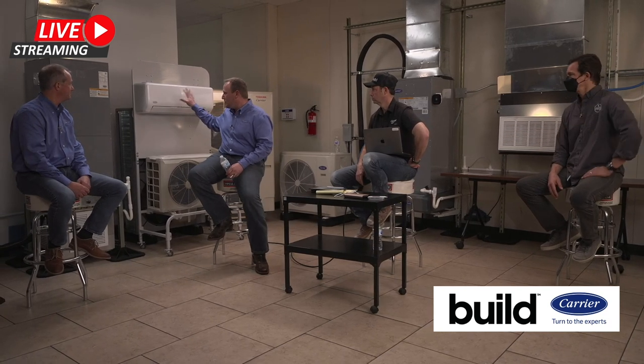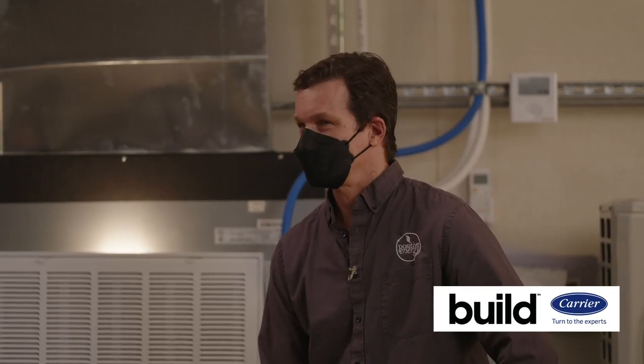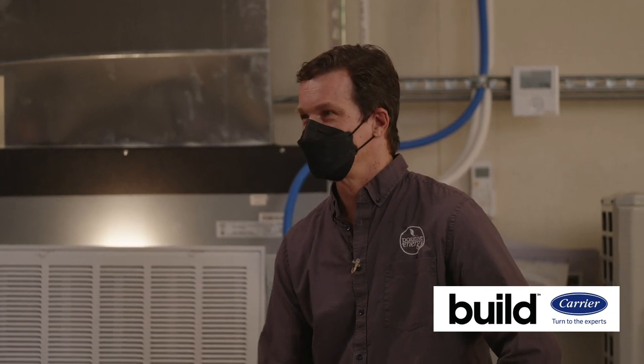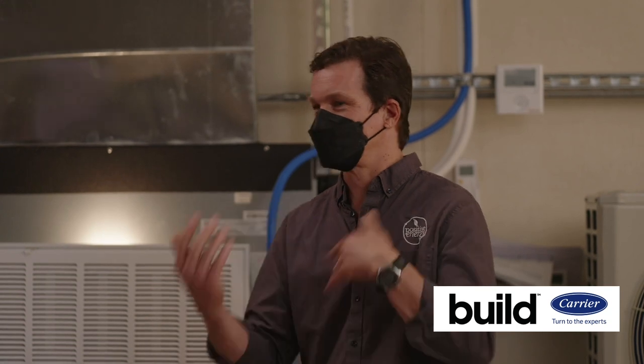But from a maintenance perspective, of course you want to clean your filter. The other thing that happens with these units, and those of you with experience with them, especially contractors and homeowners that have had them for years, eventually you're going to end up with a dirty blower wheel in here. Let me pause you for a second - in the past we've put a lot of mini splits in our houses. When you have a dirty blower wheel or a dirty unit with a coil, what's it like to get that thing clean? Oh, it's brain damage. Condensate management on these wall heads and blower wheels get caked up with dust and are just slapping the air and therefore not moving it through the space. Big problem.